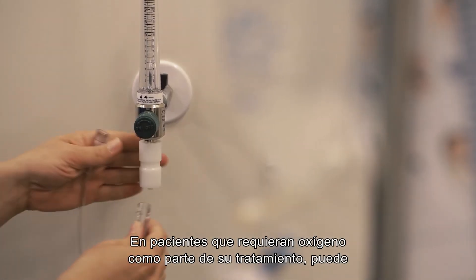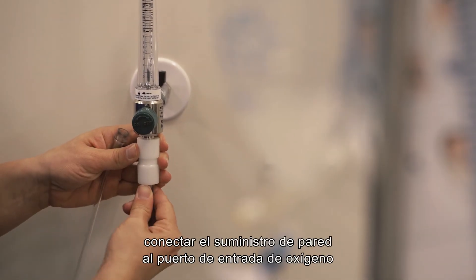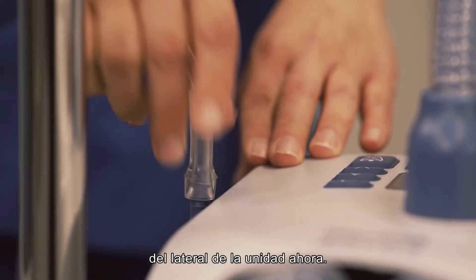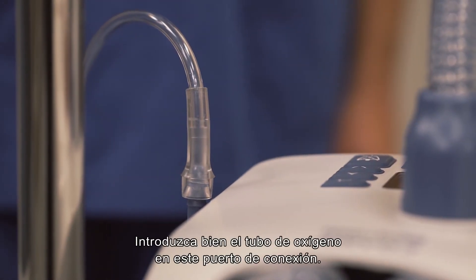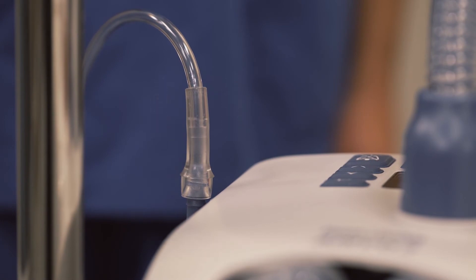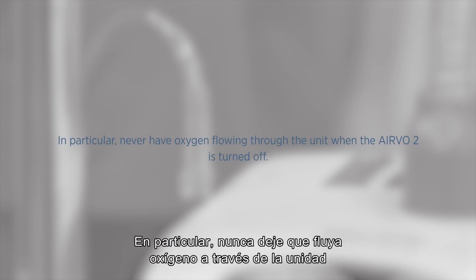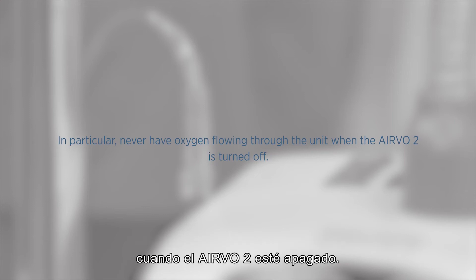For patients that require oxygen as part of their treatment, you can connect the wall supply to the oxygen inlet port on the side of the unit. Make sure you push the oxygen tube firmly onto this connection port. Be sure to read the oxygen warnings in the AIRVO 2 user manual before using oxygen. In particular, never have oxygen flowing through the unit when the AIRVO 2 is turned off.